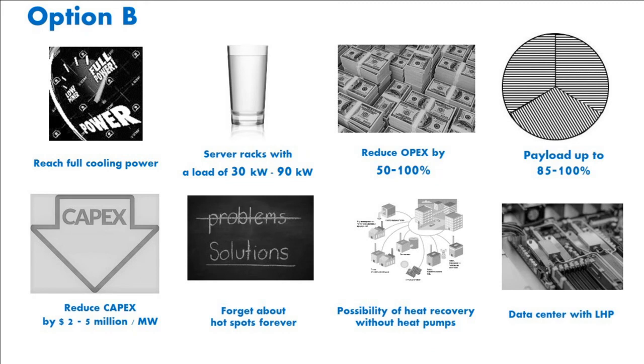Now we will consider another option where we can achieve the required cooling power in the entire load range, use racks with a load of up to 90 kW, conditionally reduce operating costs to 100%, achieve IT load conditionally 100% of the full data center capacity, reduce CAPEX by $4 million per megawatt, build a data center without problems in future operation, with an additional source of income, and get an affordable alternative to immersion cooling.